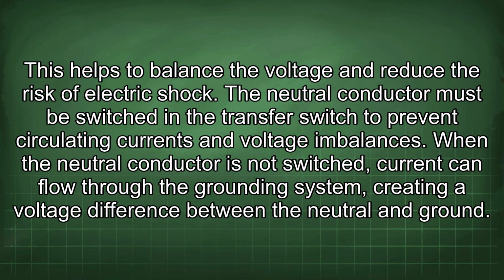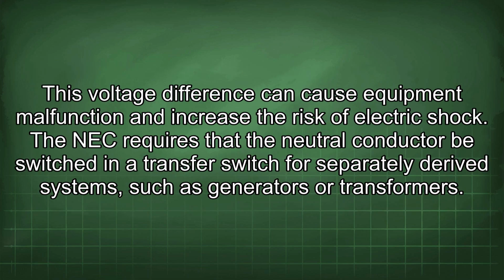The neutral conductor must be switched in the transfer switch to prevent circulating currents and voltage imbalances. When the neutral conductor is not switched, current can flow through the grounding system, creating a voltage difference between the neutral and ground. This voltage difference can cause equipment malfunction and increase the risk of electric shock.